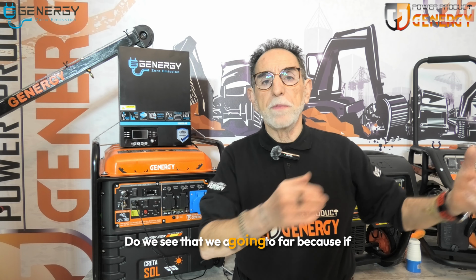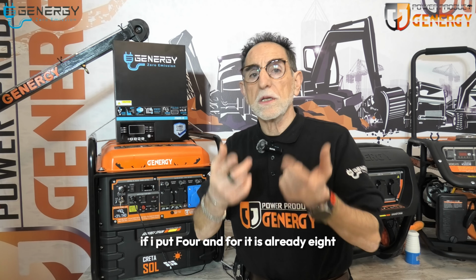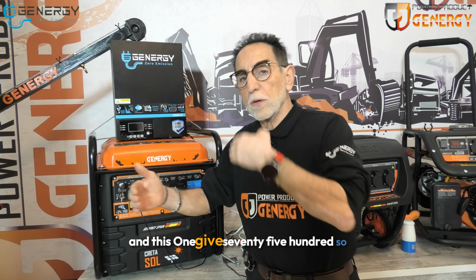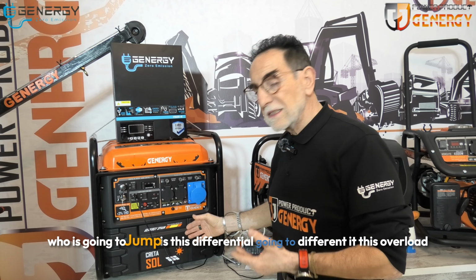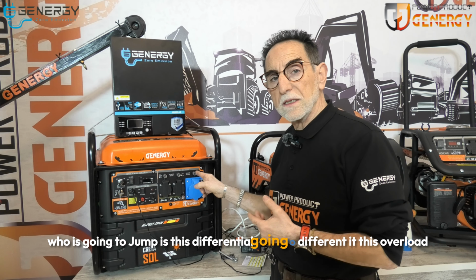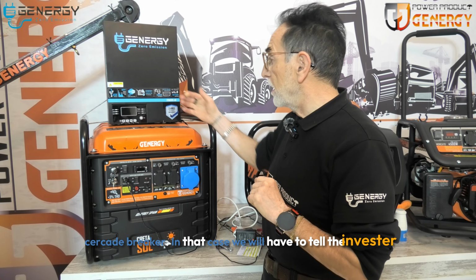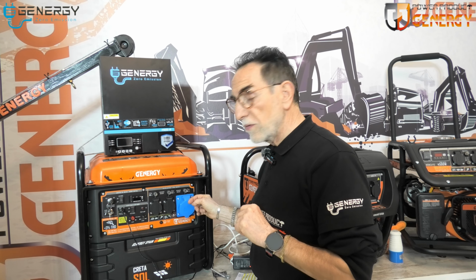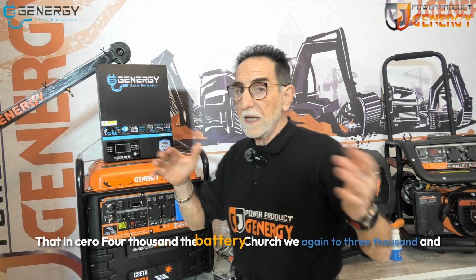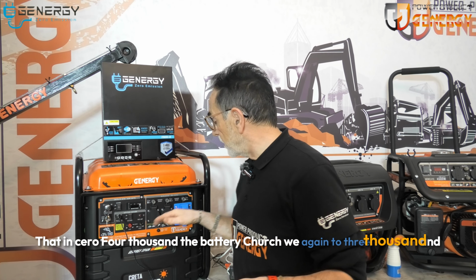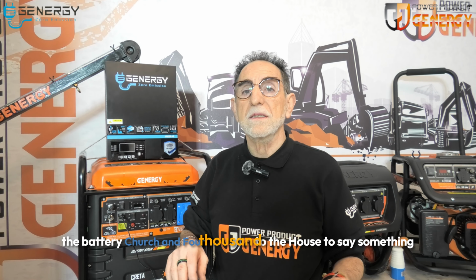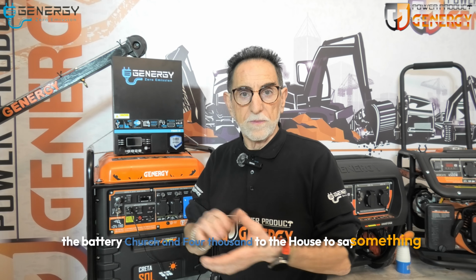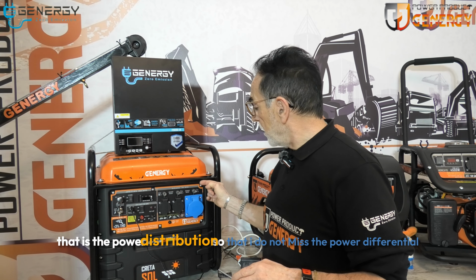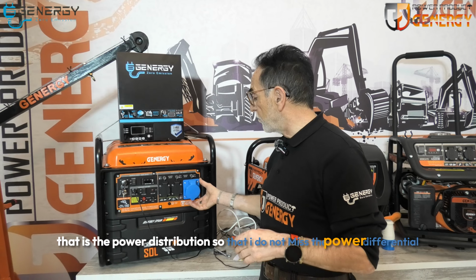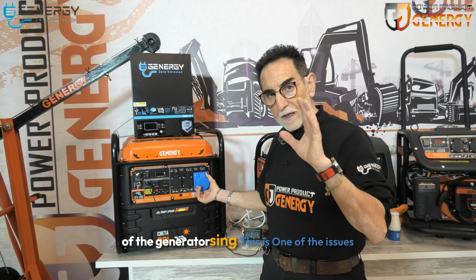Do we see that we are going too far? Because if I put 4 and 4, it is already 8. And this one gives 7500. So who is going to jump? Is this differential going to trip this overload circuit breaker? In that case, we will have to tell the inverter so that this does not happen. Instead of 4000 for the battery charge, we are going to tell it to put 3000 for the battery charge and 4000 to the house. That is the power distribution, so that I do not trip the power differential of the generator.